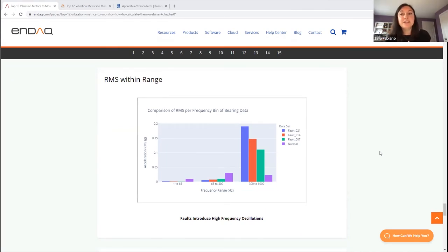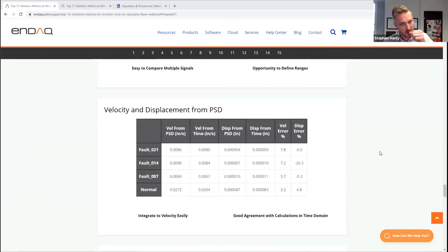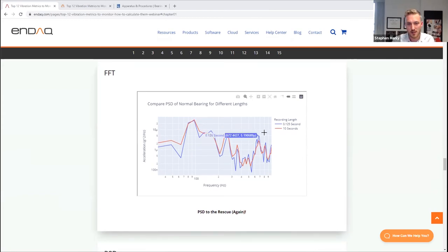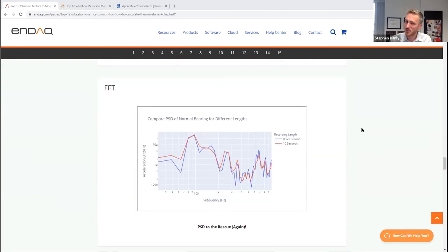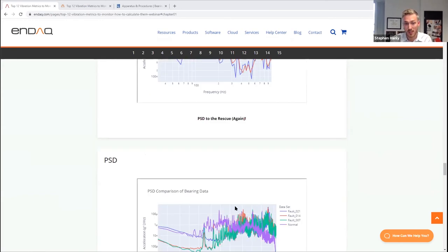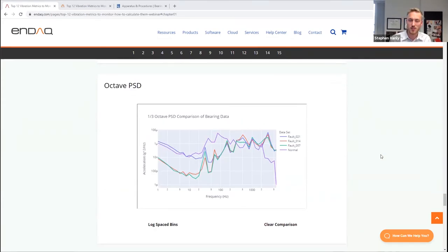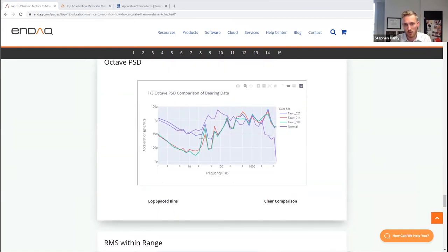Question: Could you explain the difference between the random vibration PSD and the PSD introduced here? I'm not sure I fully understand the question — this is the PSD of the bearing data. If I plotted the octave-spaced version on top of the high-resolution one, you'll see they're at the same levels; it almost looks like an average of them. Question: Is there a particular method that is best for determining natural frequency? It would be looking at a relatively high-resolution PSD and pulling out the peak. With real-world vibration profiles having many natural frequencies, I like looking at the one-over-one octave and finding the peak within each octave range to track resonances across certain frequency bands.